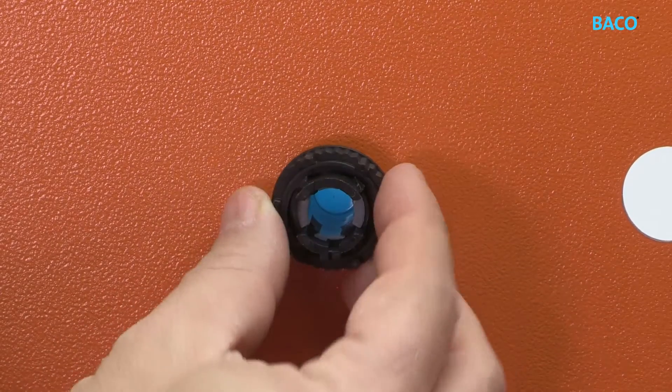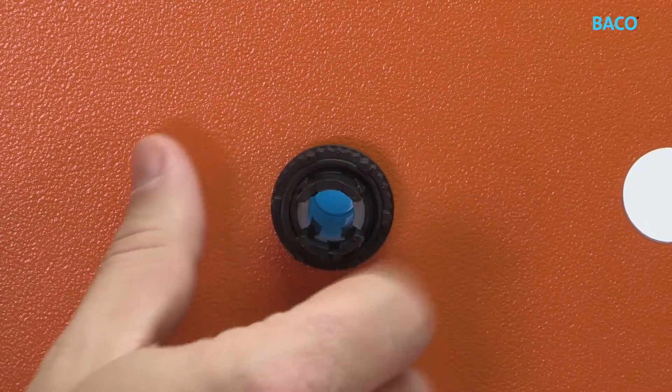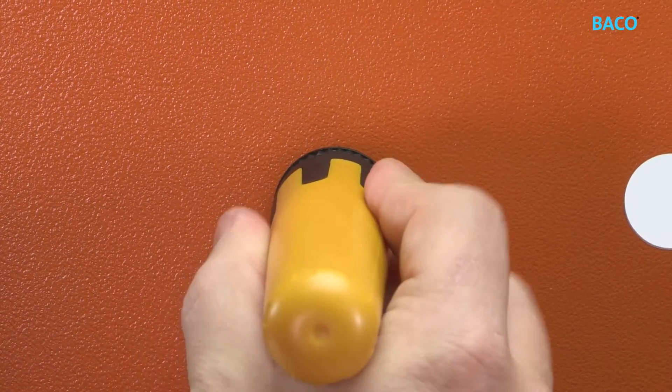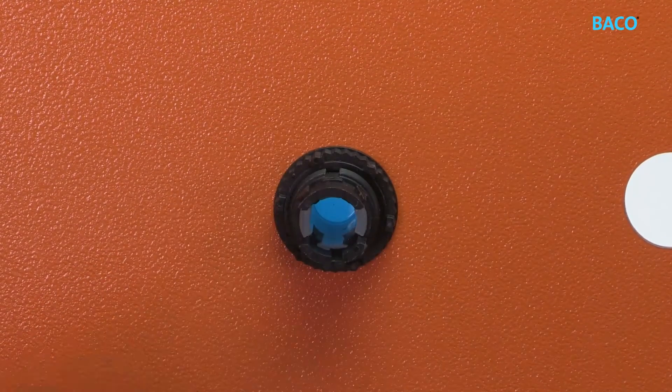Now add the mounting ring using the appropriate tool, the BACO tightening wrench LWA0234. The recommended torque is 3Nm.